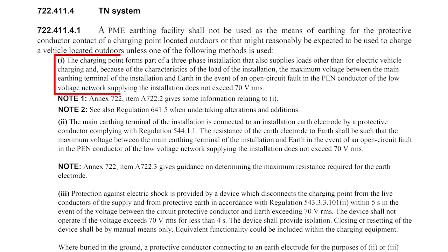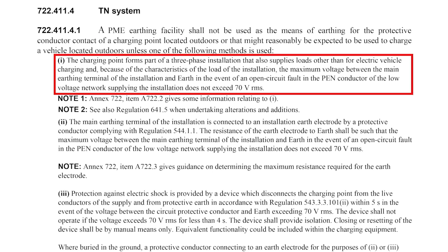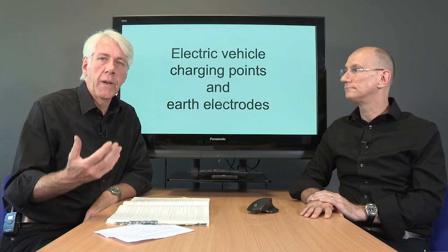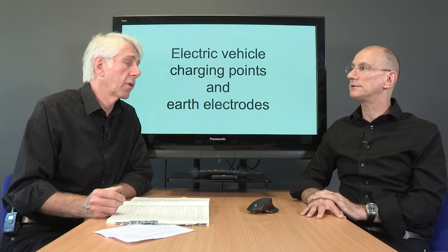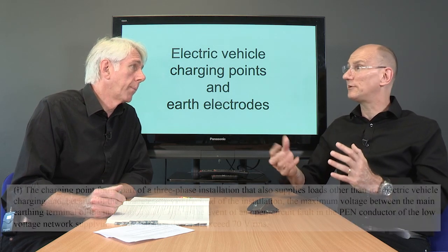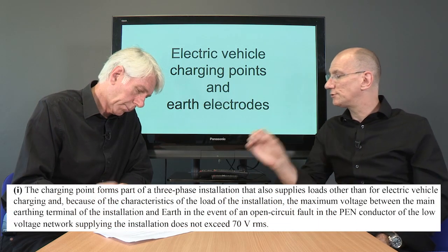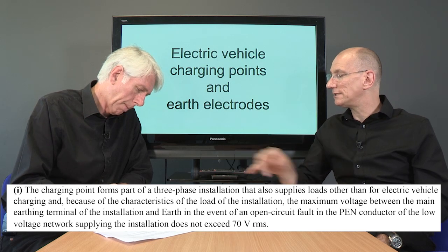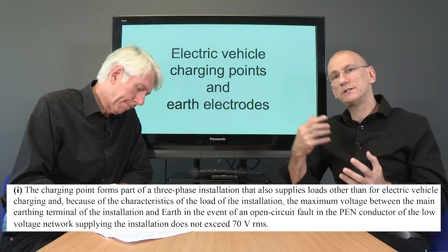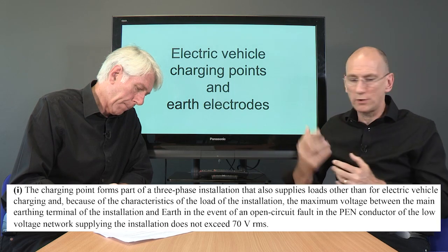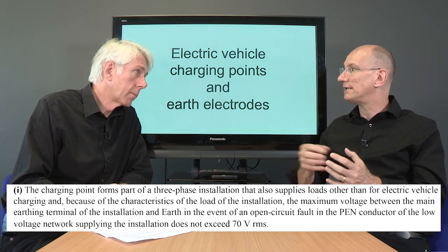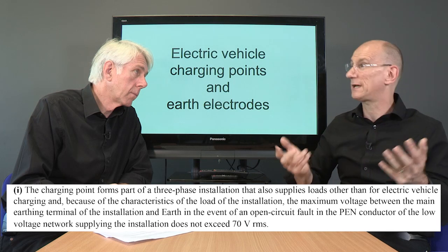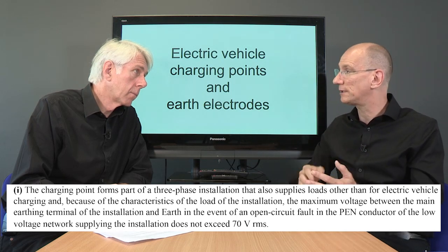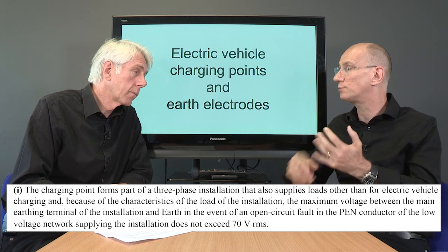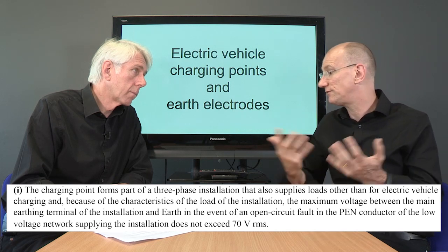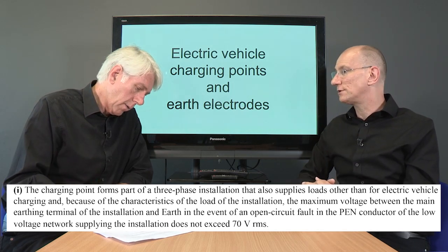Now the first one really is looking at the three-phase side of things, which we feel isn't going to affect a lot of the domestic installs. Well, not for the short time, but there will be maybe for the long time for fast charging. Yeah. But when you come to look at the requirements in that situation there, and we did cover this in the last video, is that you've got to monitor the loads and how they're balanced. And I don't mean for a day or popping in a couple of times a week. This could be 4 months, because you've got different cyclical loads, winter, summer, different times, shifts and all that sort of thing. So it's pretty difficult to do.